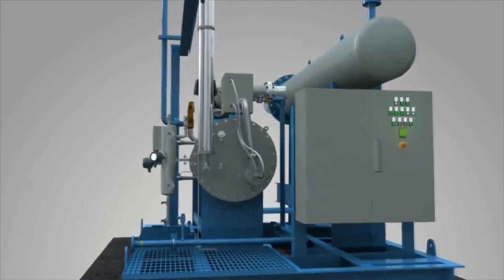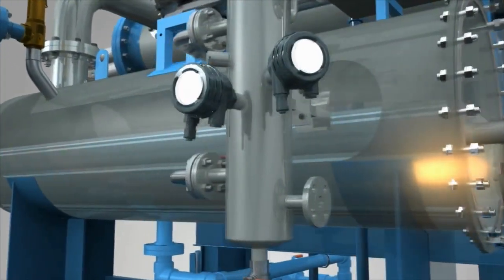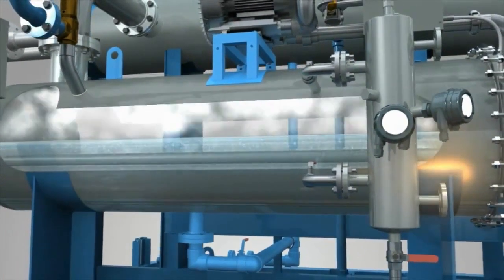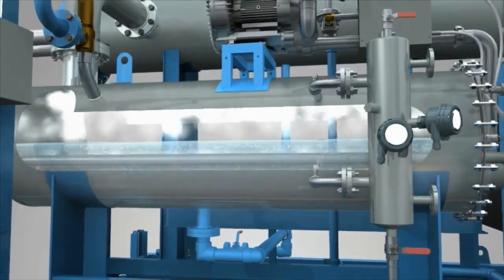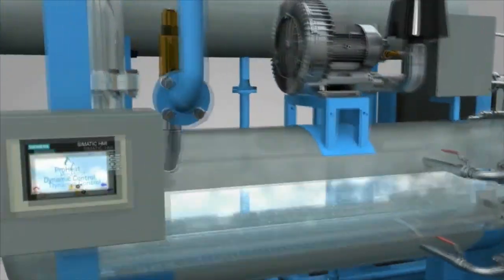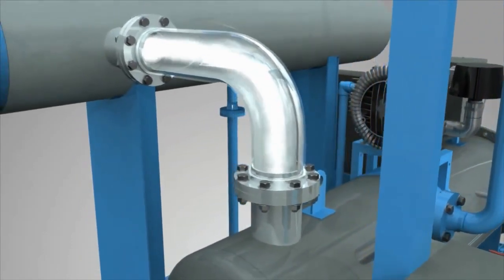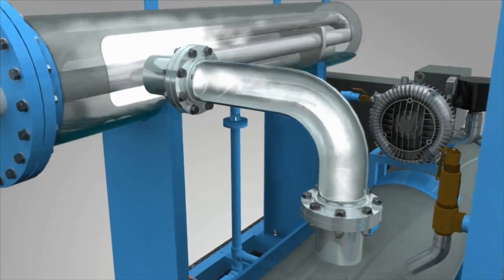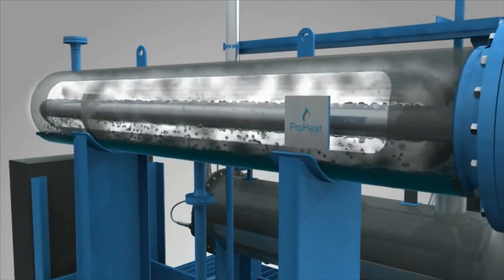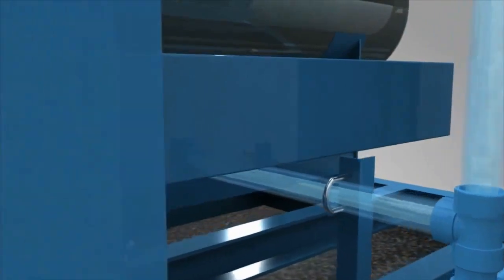The heart of our system is the Immersion Burner. We fire a flame inside a fire tube, transferring energy to a bath of water and glycol. As new energy is added to the system, it takes only a few seconds for steam to form. We chose to operate under vacuum because it saves energy, creating steam at 40 to 80 degrees Celsius. Steam travels upwards to a heat exchanger which contains a continuation of the natural gas pipeline. As steam finds the pipe surface, it transfers energy by recondensing to liquid water before traveling by gravity back to the evaporator.